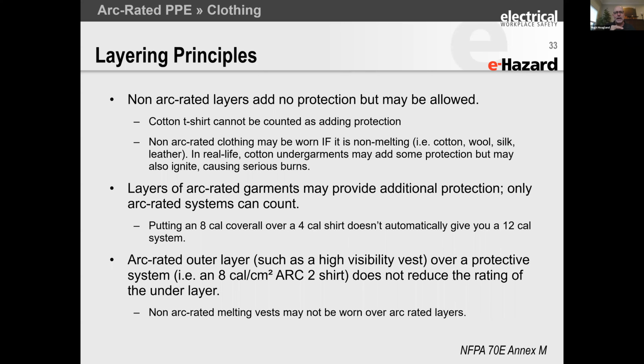So if you have an arc rating of 8 and you get 20 calories, will you ignite a cotton t-shirt? Almost every time. And if you ignite a cotton t-shirt, it's almost as if you didn't have on the arc-rated clothing. So you have to be really careful that you match it to the hazard. If you're going to allow cotton clothing, you never want to wear melting clothing underneath.